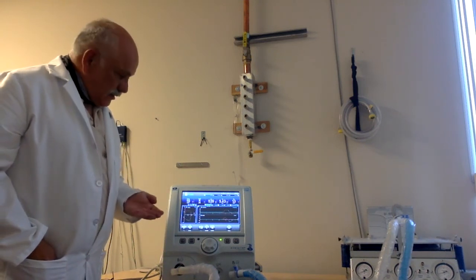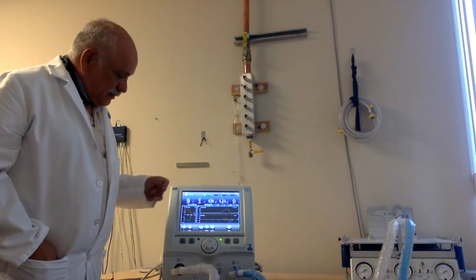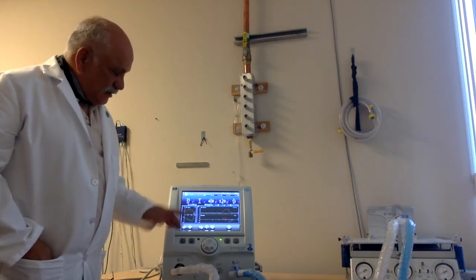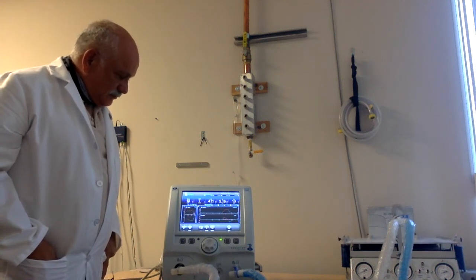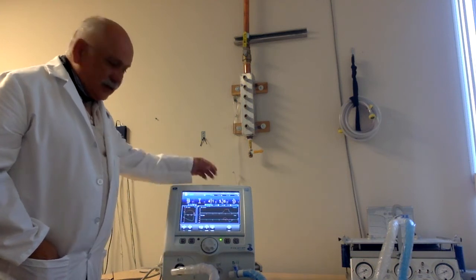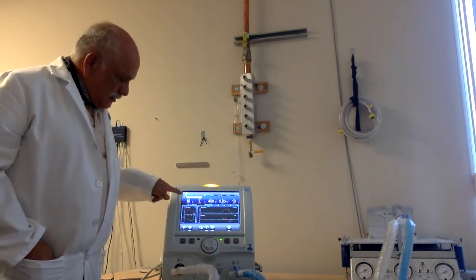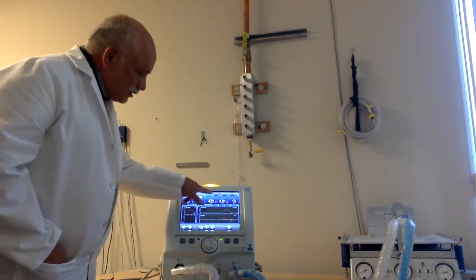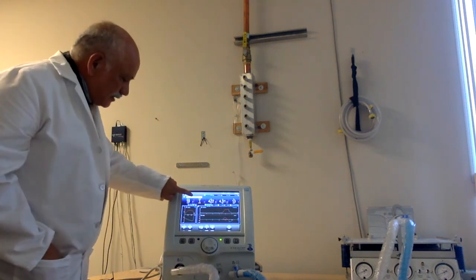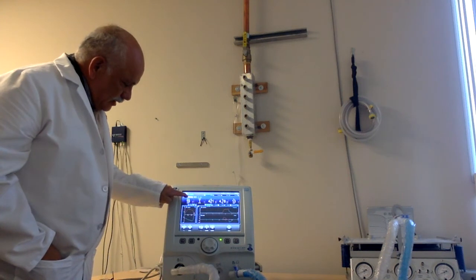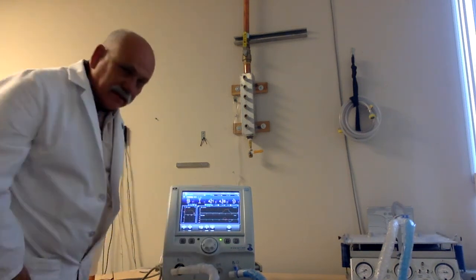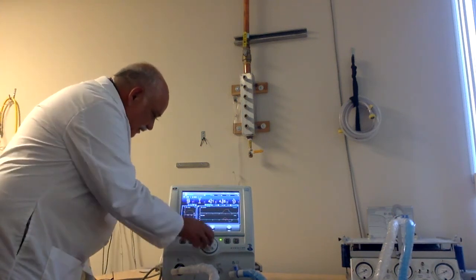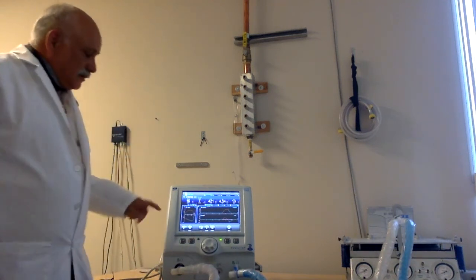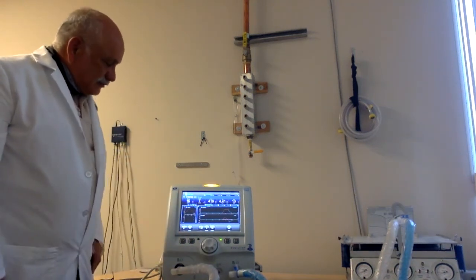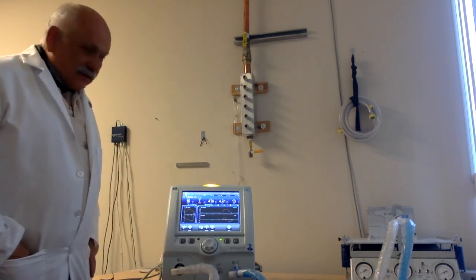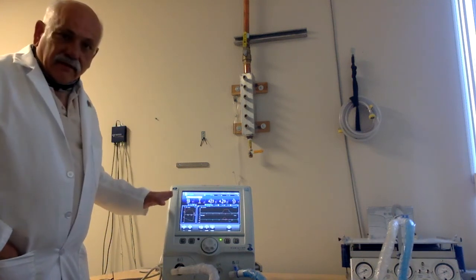And as soon as we get a breath and it starts to hit the baseline, my PEEP alarm is going to come up. So right now my PEEP has hit 1. Next breath, we should start to get an alarm. There we go. It's telling me on the screen there's low PEEP. Now I could go to the alarm setting, or I could simply touch the alarm indicator itself, see that PEEP is low. If it's something I intended to do, then I can easily adjust my low PEEP. I touched, I adjusted, I turned, and I accepted. Now, after a few breaths, we'll notice the alarm is cleared.